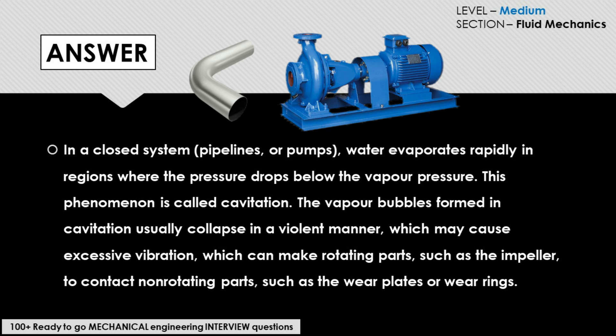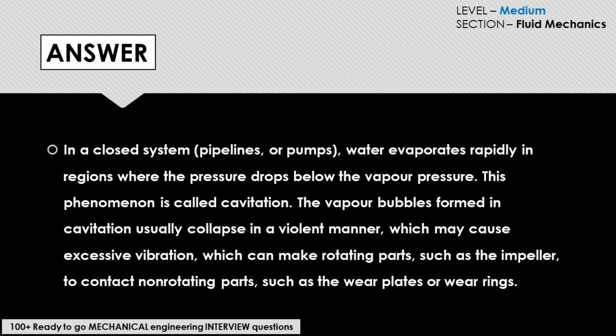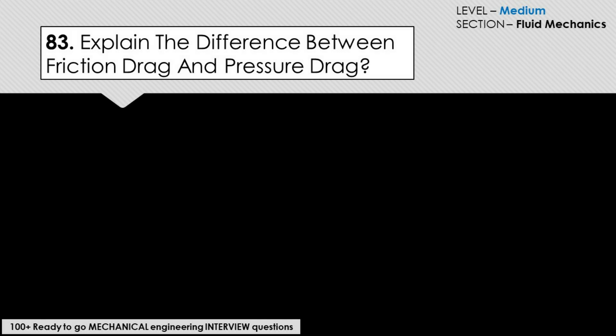The answer: in a closed system like a pipeline or pump, water evaporates rapidly in regions where the pressure drops below the vapor pressure — this phenomenon is called cavitation. The vapor bubbles formed in cavitation usually collapse in a very violent manner, which may cause excessive vibration that can make rotating parts such as an impeller contact non-rotating parts such as the wear plates or wear rings.